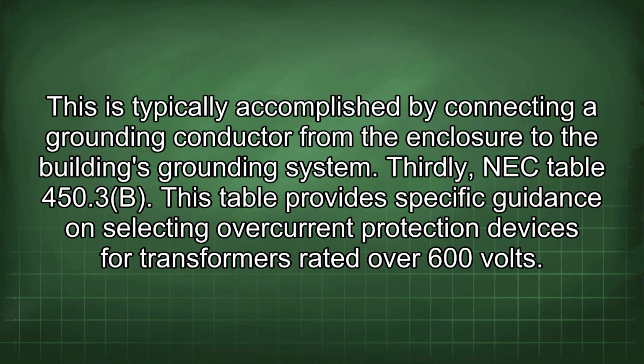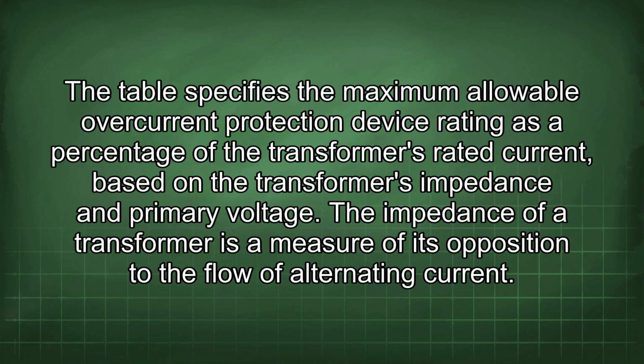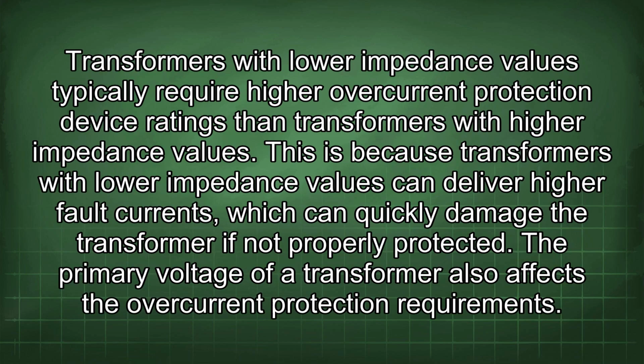Thirdly, NEC Table 450.3(b). This table provides specific guidance on selecting overcurrent protection devices for transformers rated over 600 volts. The table specifies the maximum allowable overcurrent protection device rating as a percentage of the transformer's rated current based on the transformer's impedance and primary voltage. The impedance of a transformer is a measure of its opposition to the flow of alternating current. Transformers with lower impedance values typically require higher overcurrent protection device ratings than transformers with higher impedance values.